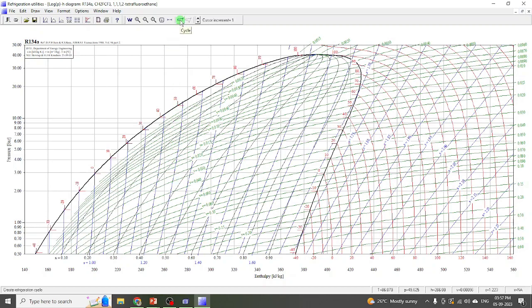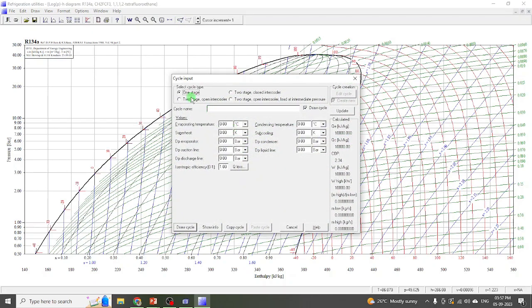Now we have to put the values. Click on the cycle icon. Here you can choose whether it is a one-stage or two-stage cycle, whether there is an intercooler or not, and all such things. For this simple problem, let's put the evaporating and condensing temperature. Our evaporating temperature is minus 10 degree centigrade and condensing temperature is 40 degree centigrade.